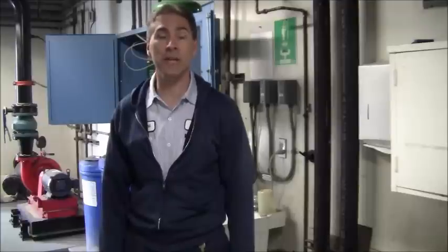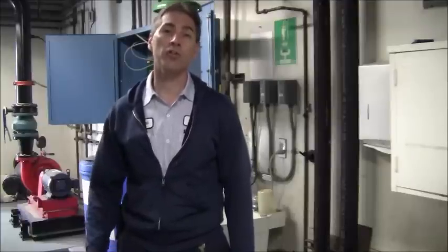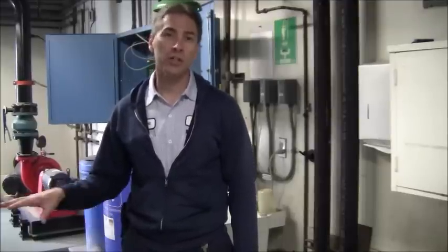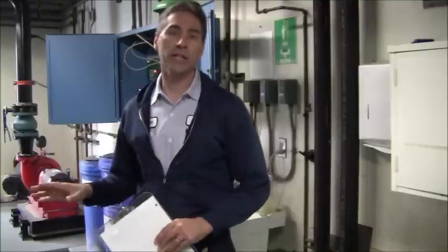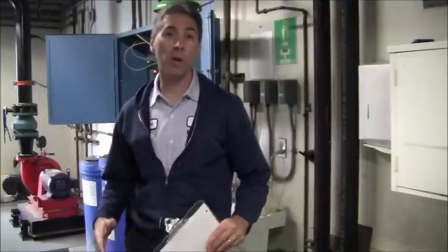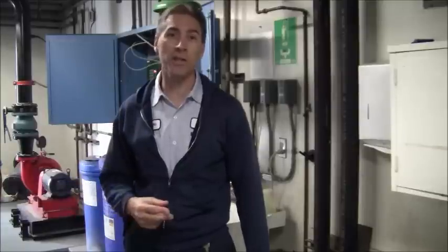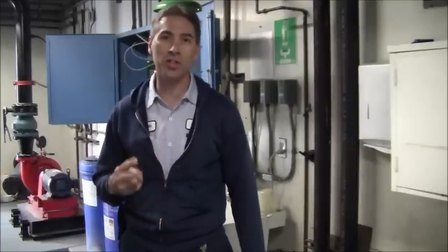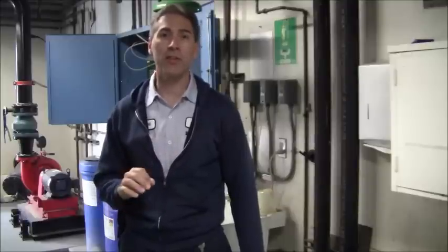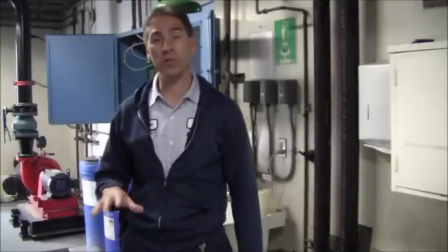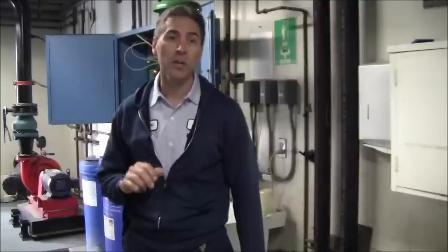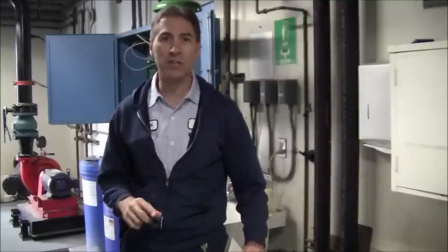Today's training is going to be on water treatment. The water treatment is for chillers and cooling towers. When we talk about water treatment when it comes to chillers, there's basically two loops of water in the chiller. There's the chilled water, which is a closed loop, and there's the condensing water, which goes to our cooling tower outside, which is an open loop, and they get treated differently.